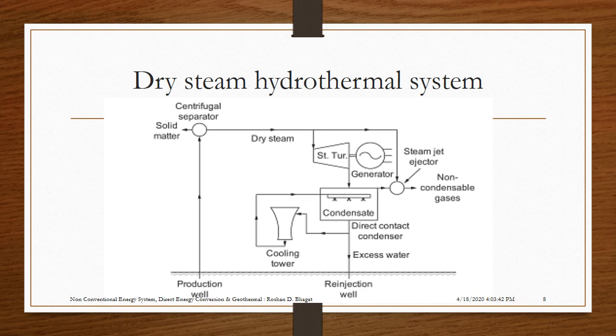Dry steam is passed to the turbine, which rotates the turbine blades. The shaft of the turbine is coupled to the generator, which generates electricity. The steam condenser condenses the steam coming out of the turbine by using cold water to absorb the heat. A cooling tower cools the water used in the condenser. Excess water is sent back to the injection well. The steam jet ejector separates out non-condensable gases.